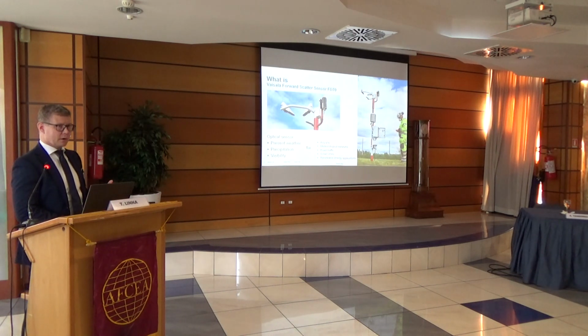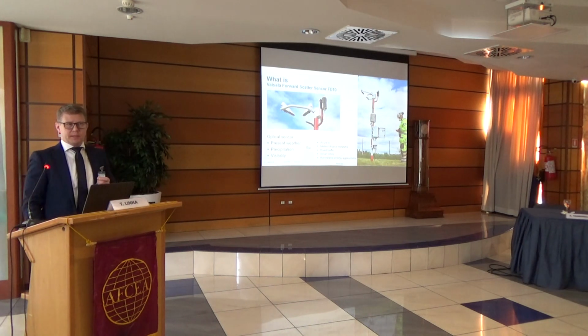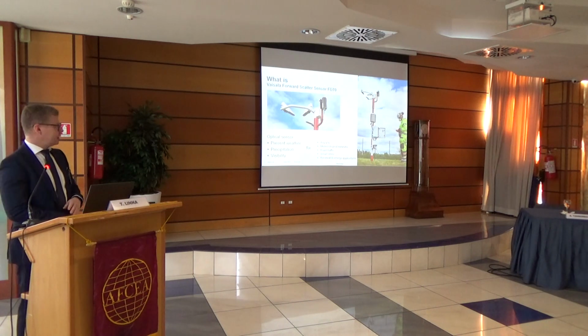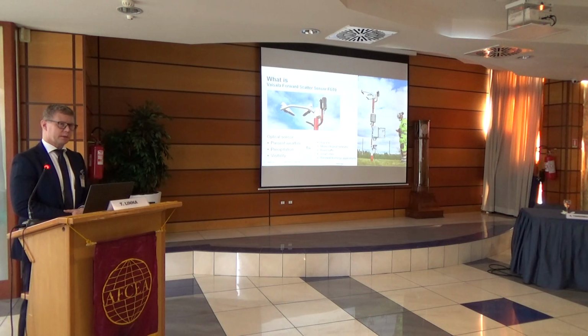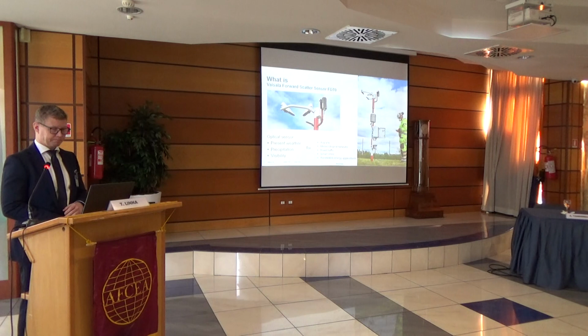It is an optical weather sensor installed at the surface, observing what the precipitation is, what the obscuration of the atmosphere is, how far one can see for visibility, the MOR, the meteorological optical range. It also has some other very specific details when it comes to identifying a huge variety of different precipitation particles. Here I only list a few applications, but only our imagination is the limit for what we can use it for when it comes to meteorological observations. Main applications for the present have been airports and meteorological networks.